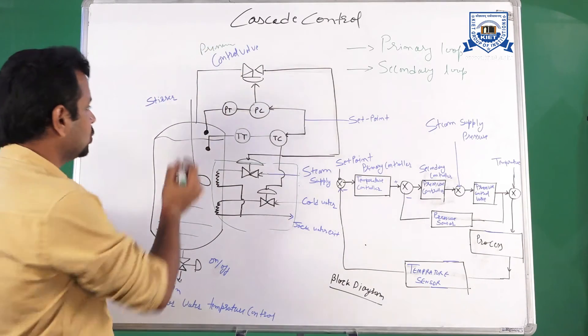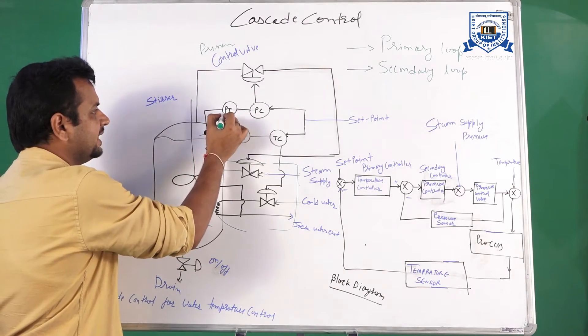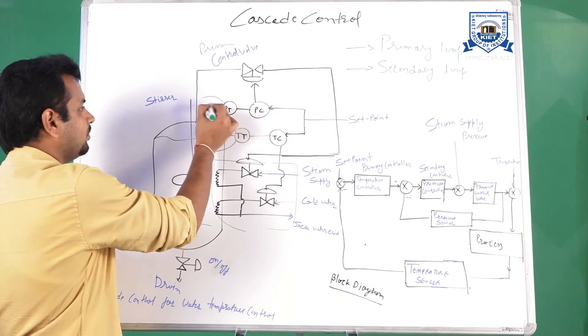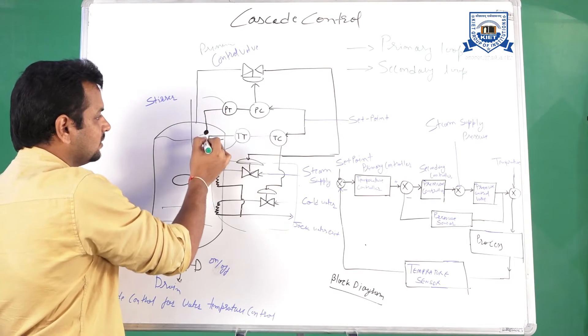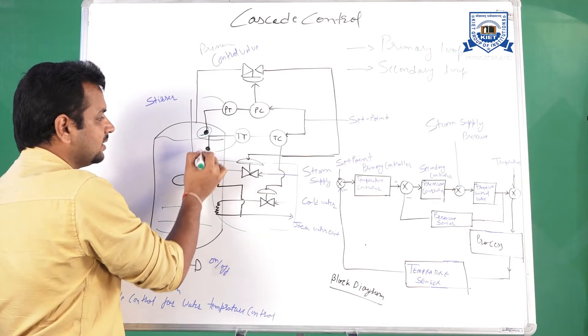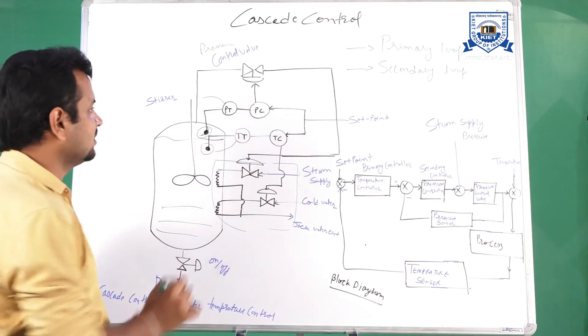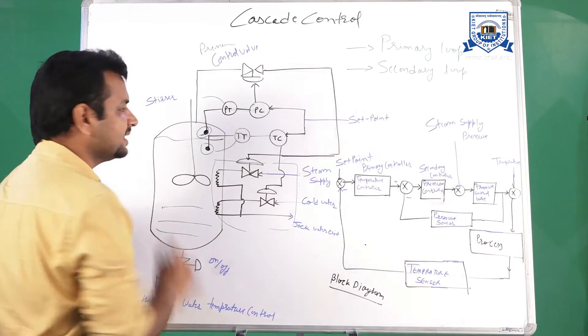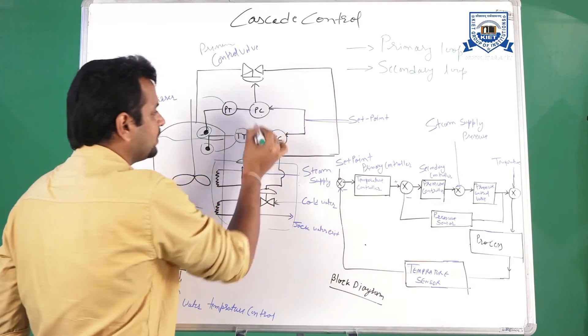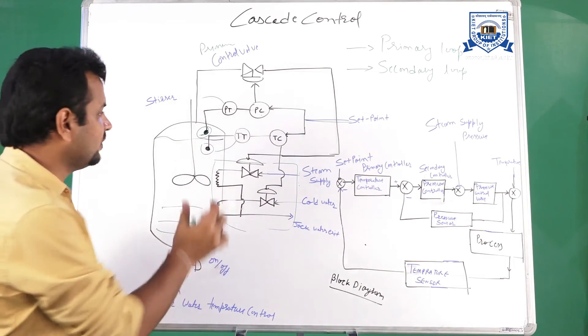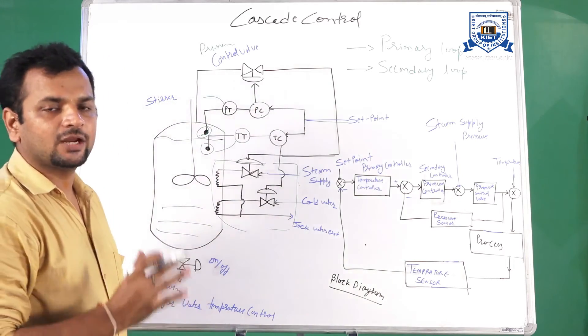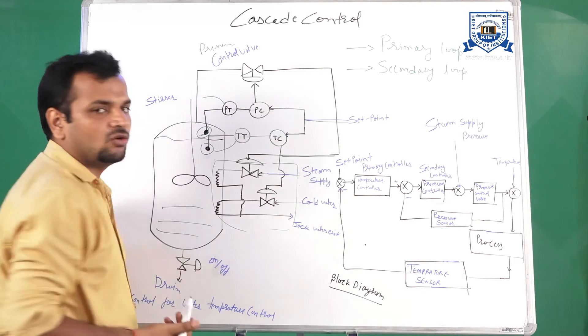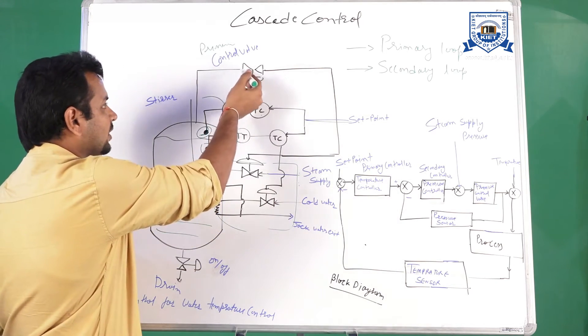Two sensors are used: PT is the pressure transmitter and TT is the temperature transmitter. The pressure transmitter measures the pressure from its sensor, and the temperature transmitter measures the temperature from its sensor. Once we know the current values of pressure and temperature, we compare them with the set point values for both pressure and temperature. Based on that comparison, we do the opening and closing of the valves — for temperature, the steam supply and cold water valves are used, and for pressure, the pressure valve is used.